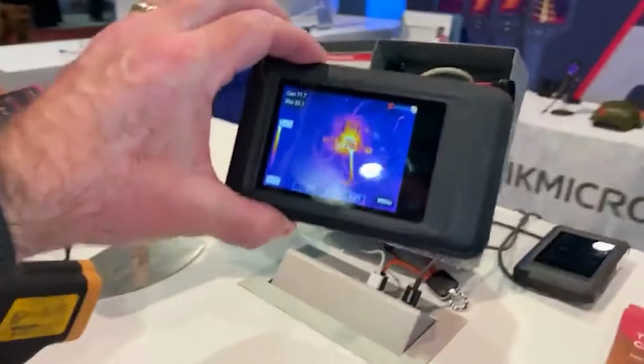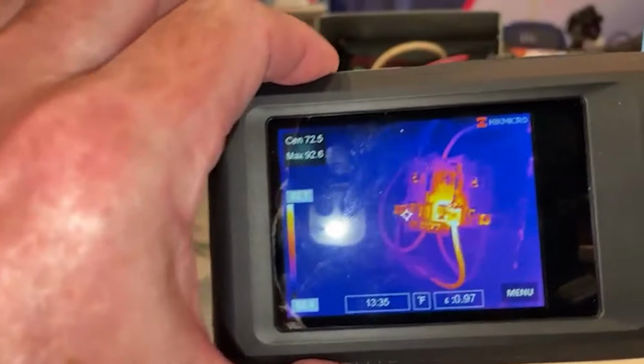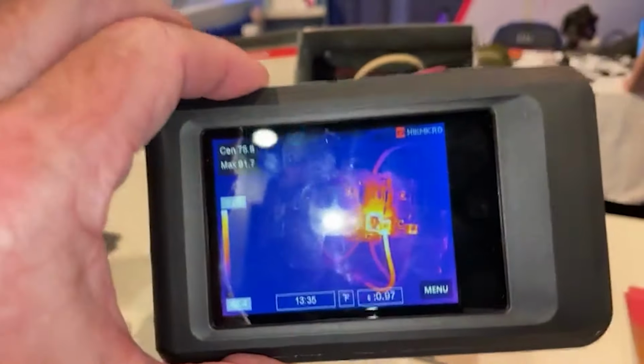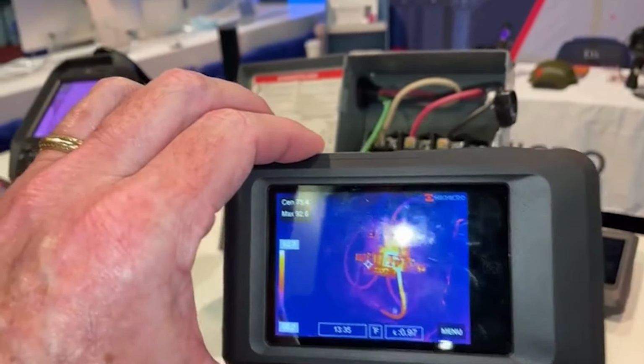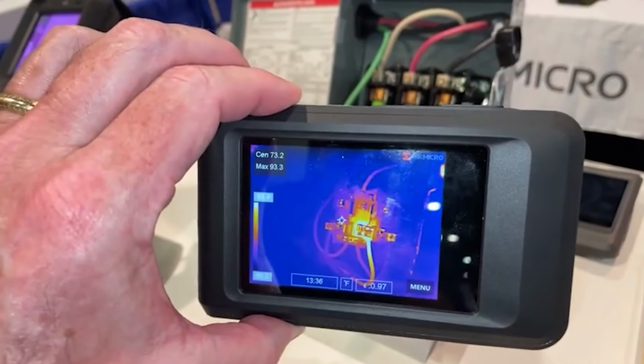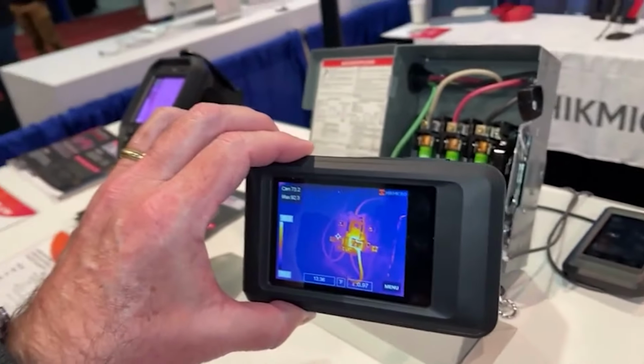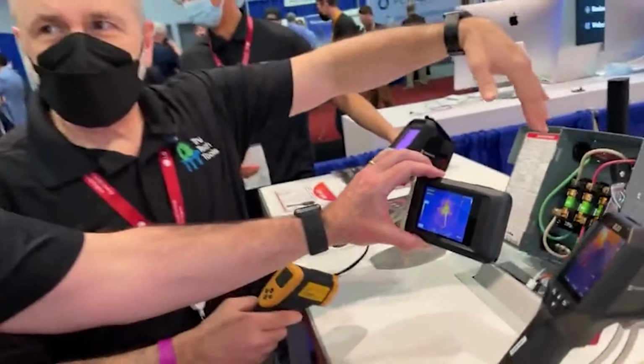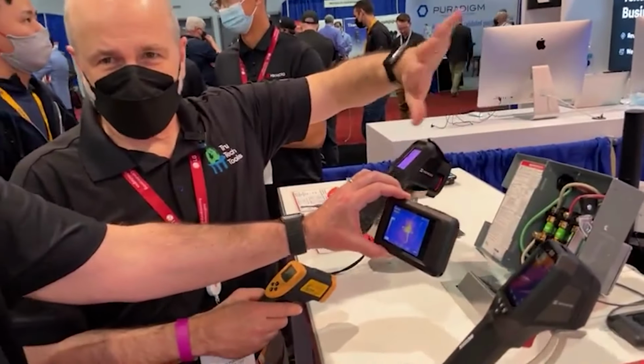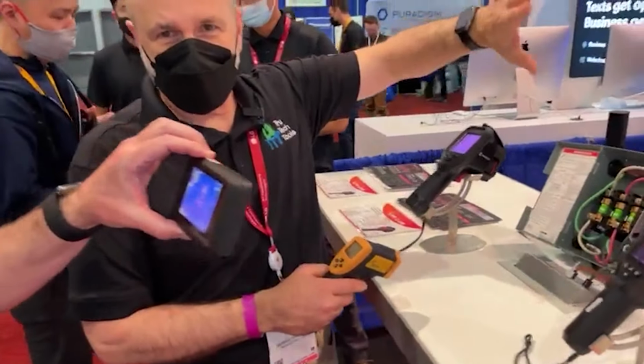Versus with an infrared camera, I instantly see which one of these is warm, and I can measure that temperature to determine: is it a problem I need to fix right now, or is it a problem that I need to fix next outage, or just monitor? At a distance too, which for electrical, has safety factors and issues like that.